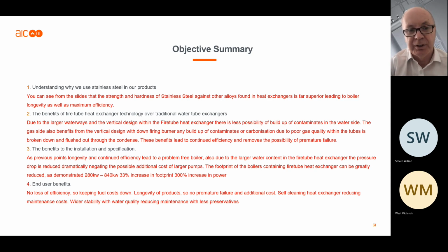Okay. The benefits to the installation and specification. Well, again, longevity of the product is key. Footprint is also a big factor as plant rooms get smaller. So you can see the benefit there of having a smaller single heat exchanger boiler, and ultimately the end user benefits, which for me is the most important part. There's no loss of efficiency because there's no build-up of contaminants in the heat exchanger, which helps keep the fuel cost down, which is an important factor these days. Longevity of the product, so no premature failure. Self-cleaning heat exchanger, so reducing maintenance costs, and wider stability within the pH. Again, reducing maintenance costs because less preservatives have to be put into that system.